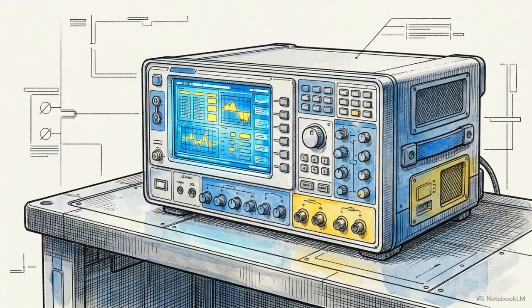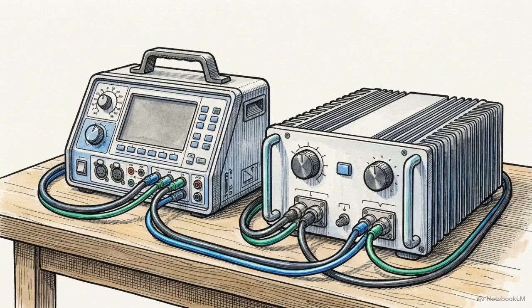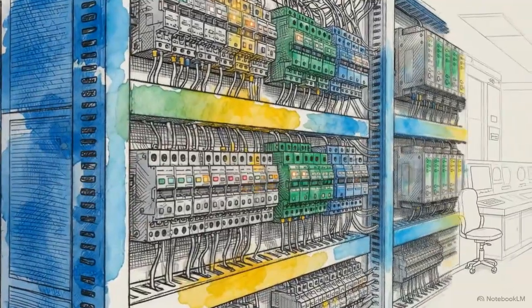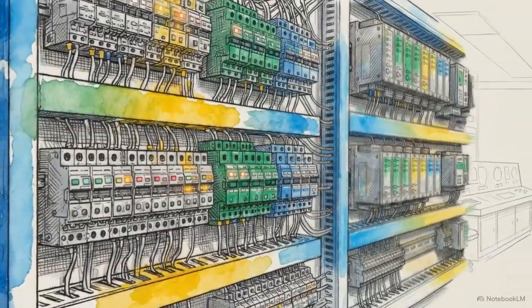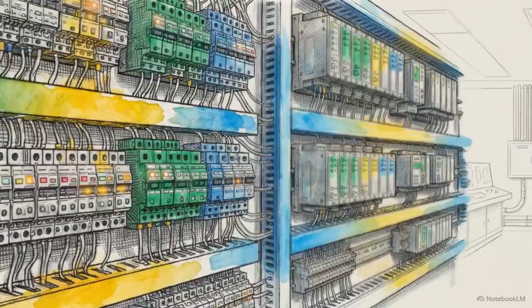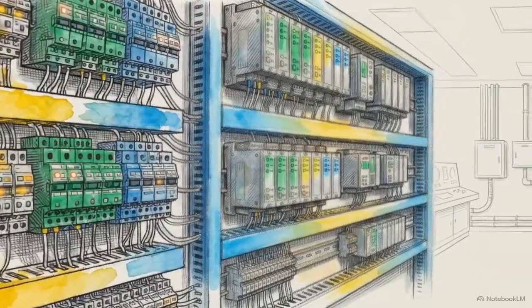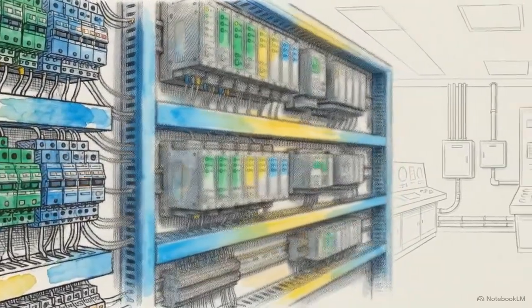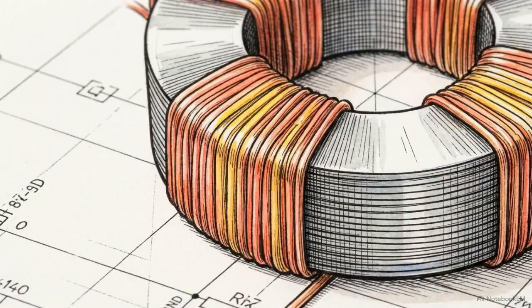The CPC100 can directly inject up to 800 amps. For substations requiring primary currents above that threshold, an external current booster is integrated into the loop. Verifying both the insulation integrity and the exact transformation ratios guarantees the protection relays will receive accurate, uncorrupted data during live operations. We then advance to the excitation and kneepoint determination test.